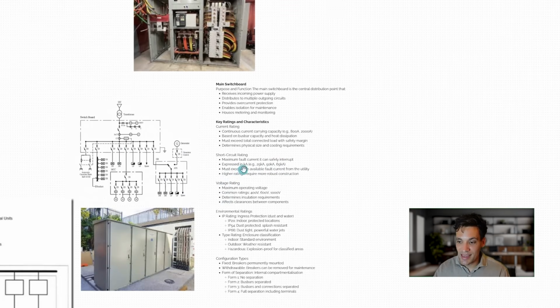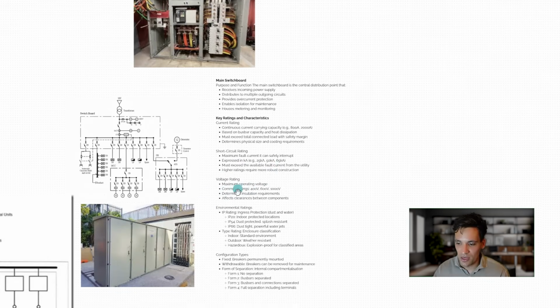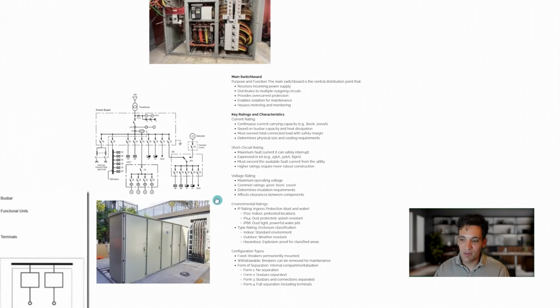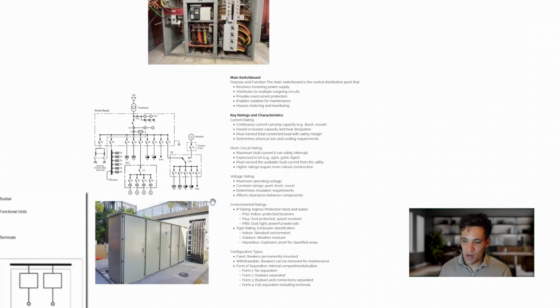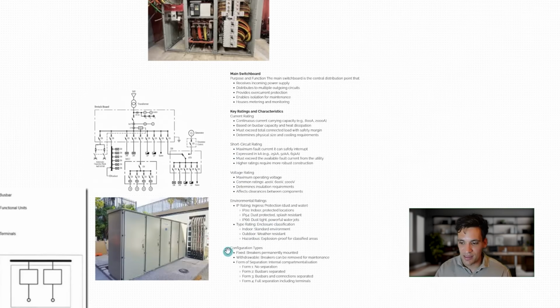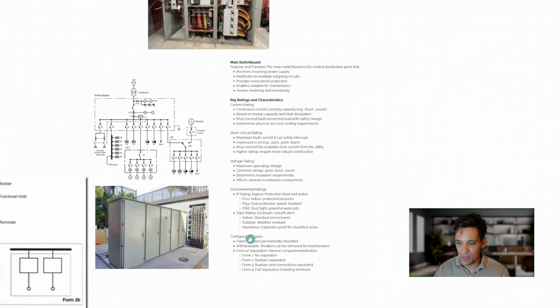There'll also be a short circuit current rating. So if there's a fault, what's the maximum fault current the distribution board can take? A higher rating will allow bigger fault currents. There's also going to be a voltage rating, which would be dependent on where you are. So a low voltage board will have less insulation. If you've got a high voltage, you might have a high voltage switchboard, which would have a lot more insulation. It might even be not air insulated, but insulated with special gases, which affects the clearances between components.